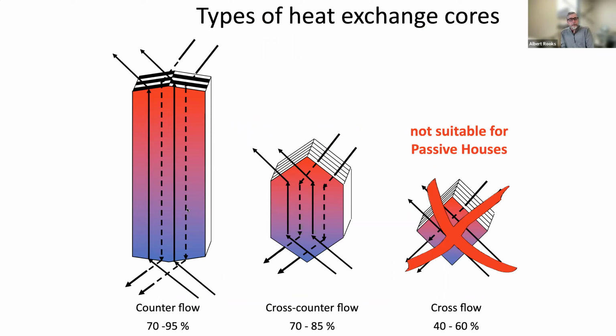And here is a picture of 3 different typical cores. This could be an HRV or it could be an ERV core. They both work the same, but essentially the longer the core or the bigger it is, the more surface area it has. And more surface area presents more opportunity for heat exchange. So as one airflow that has heat is passing by the airflow that doesn't have heat, the longer we make that journey and those 2 airflows are in proximity to each other, the more that it can transfer.